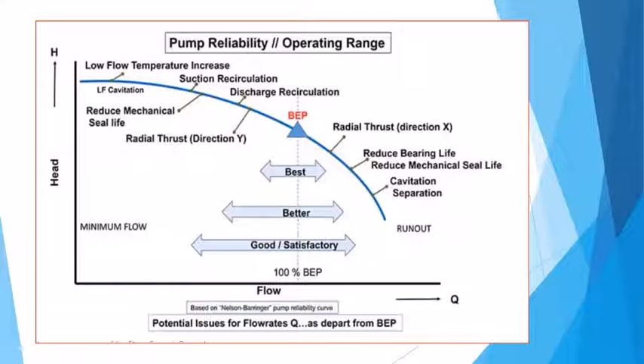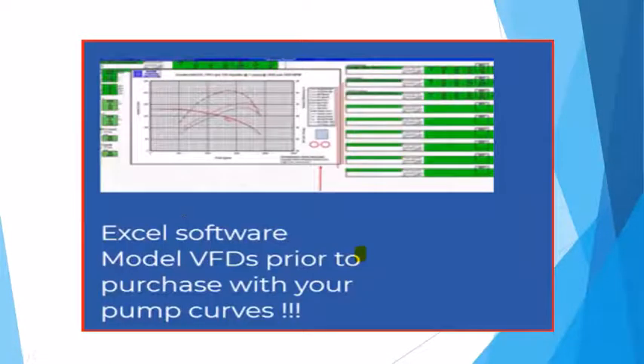So a lot of you on here are probably pump people or have experience with that. Every pump, its impeller, its speed it's designed for, its test point, has a best efficiency point of the pump. And that's typically at this point on the curve. They give you a range, this is the best range to run in, between here and here on the curve, on your efficiency. And then this is better, and then this is good or satisfactory. But you have to look at what the actual efficiency is going to be.